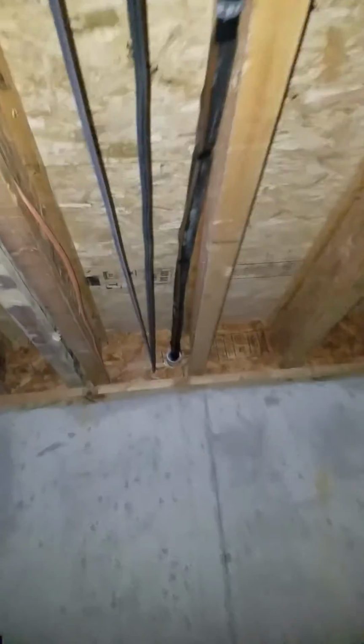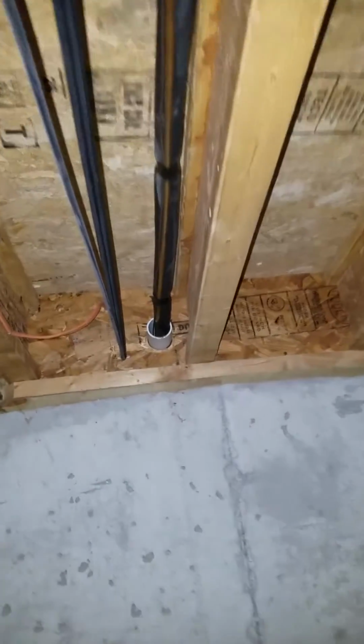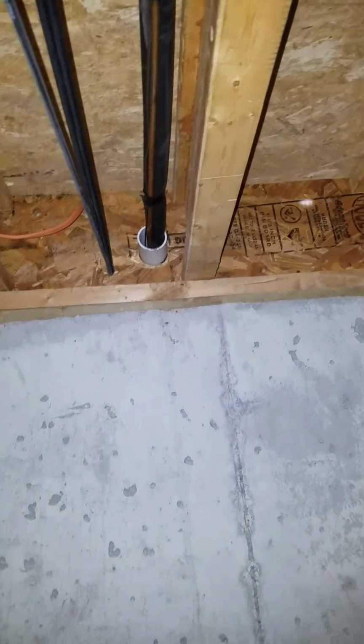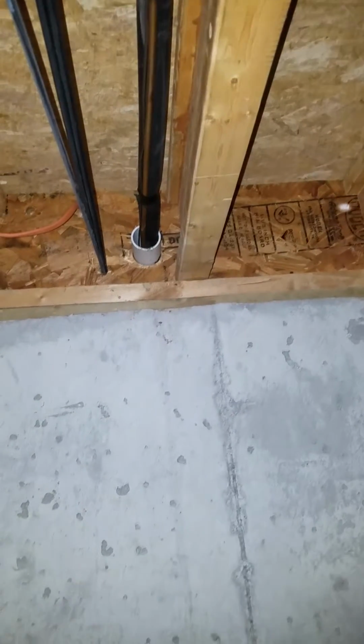Your refrigerant line is coming out of this unit, and it's running all the way like this. We're going to follow this guy, and it's going all the way over to this side of the home. So it's on the extreme opposite end. They did put a PVC pipe to run your refrigerant line through there. That's 3/8, 3/4. So that refrigerant line is about 70 foot long, if you consider going the way it's going and then going out that way.